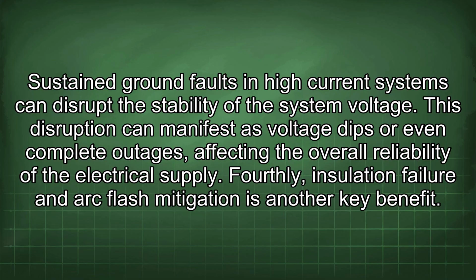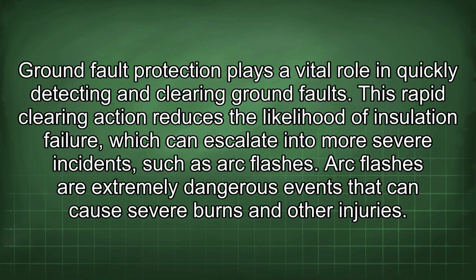Fourthly, insulation failure and arc flash mitigation is another key benefit. Ground fault protection plays a vital role in quickly detecting and clearing ground faults. This rapid clearing action reduces the likelihood of insulation failure, which can escalate into more severe incidents, such as arc flashes. Arc flashes are extremely dangerous events that can cause severe burns and other injuries.